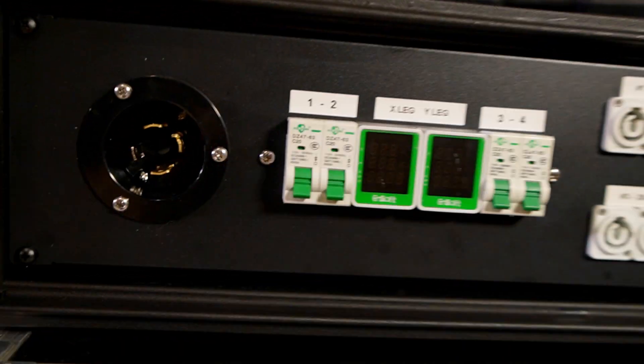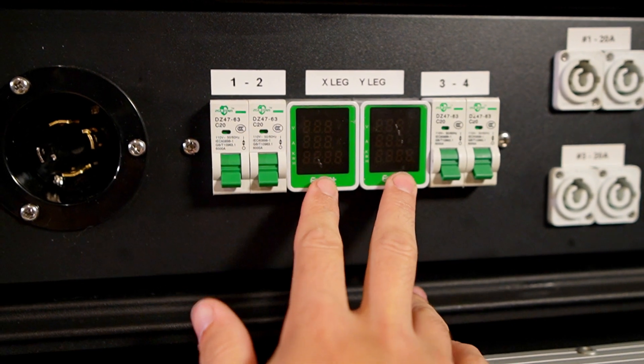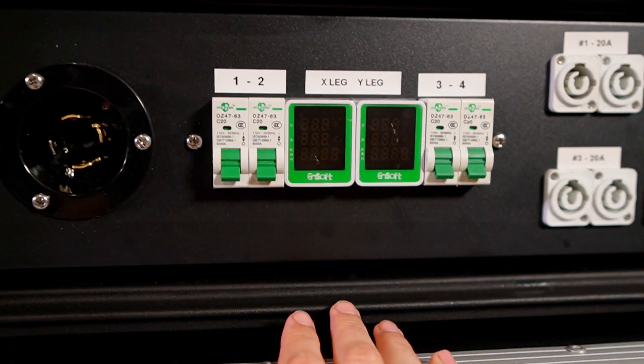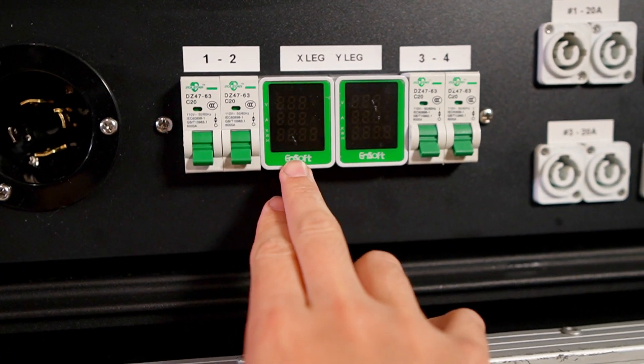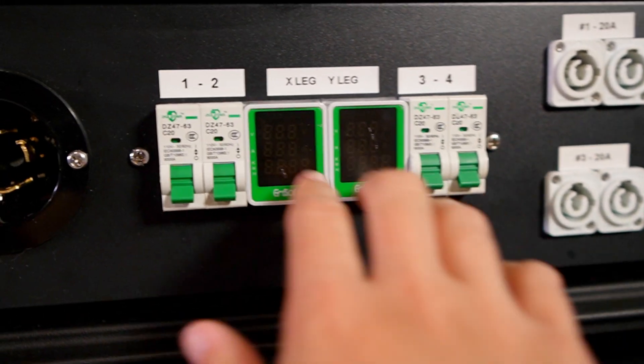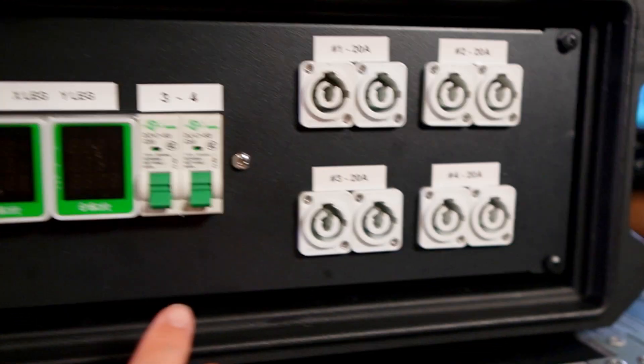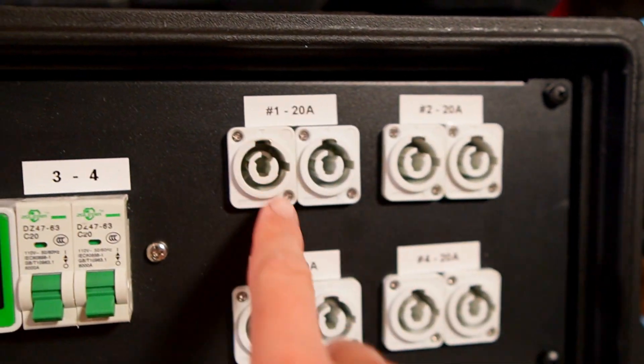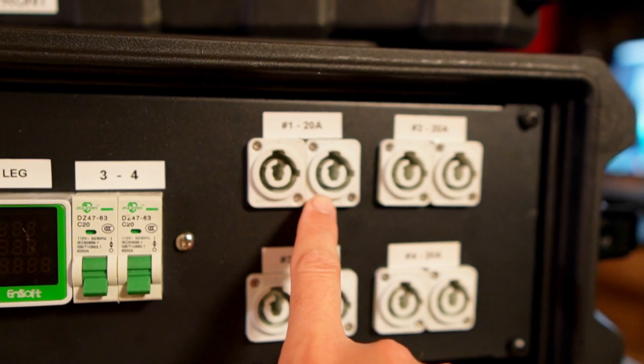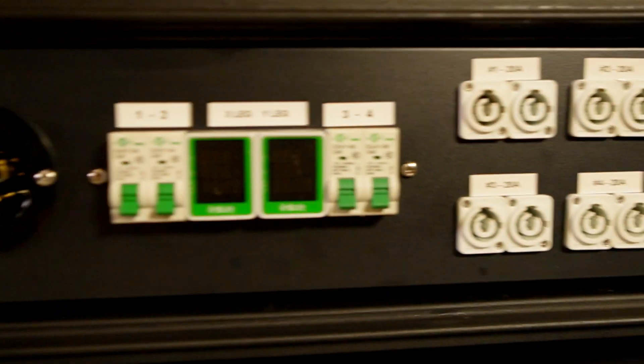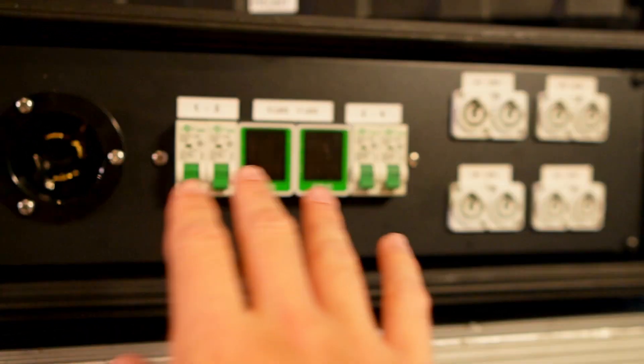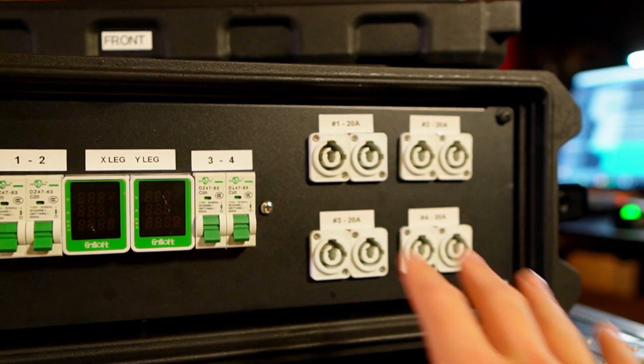So these are both tied to the two legs of the 240, so each leg of 120, each one of these are tied into. And then these split out to two 20 amp circuits, so this is like leg one, this is leg two, and there's two 20 amp circuits on each leg. And then I have two powercon outlets for each one of these four circuits. So that's really all there is to this thing, I'm just splitting out the legs and distributing it to these powercon outlets.